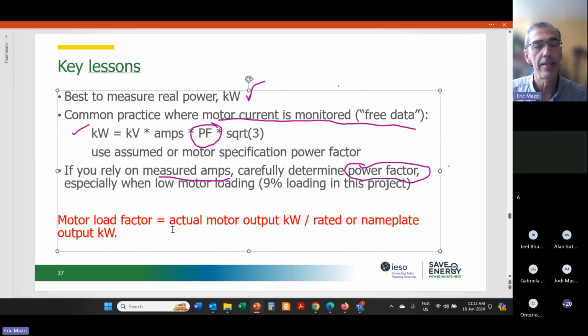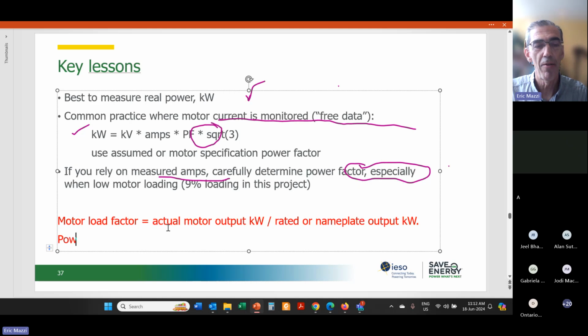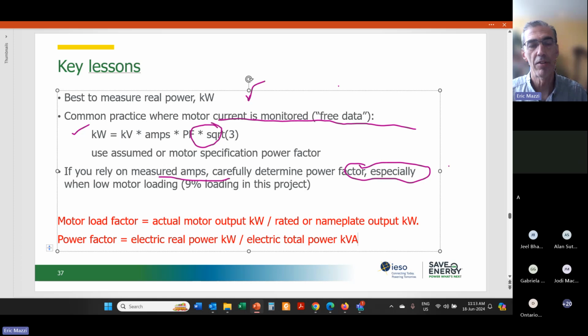It's a good question because, okay, power factor, of course, is on the electric side. It's your electric real power in kW divided by your electric total power in units of kVA. So it's a ratio of kW to kVA. It's the electricity. It's a parameter based on the electric power supply, whereas motor load factor is all on the mechanical side of the motor. I can maybe show you even a diagram here, which I think I have handy, which may only take a moment.